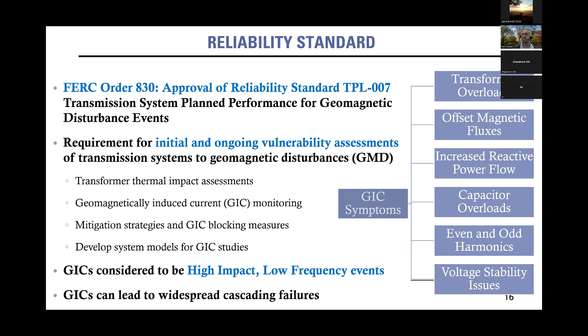Some of the solution approaches involve installing blocking devices. Now, we saw this circuit before. Is there a way you can install a filter that will disrupt the path of these GICs? The problem with that is it has not gained widespread industry acceptance, because by disconnecting this neutral from the ground, you're defeating the purpose of grounding, which is for protection and safety reasons. We keep the power system grounded. So there's not a lot of industry buy-in yet about using these in the system because it can compromise normal operation. So there's limited implementation of these devices in the network.